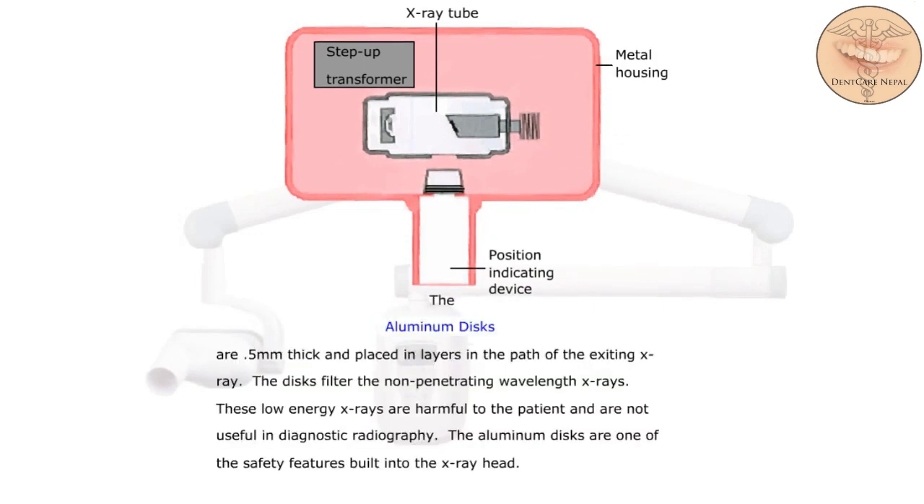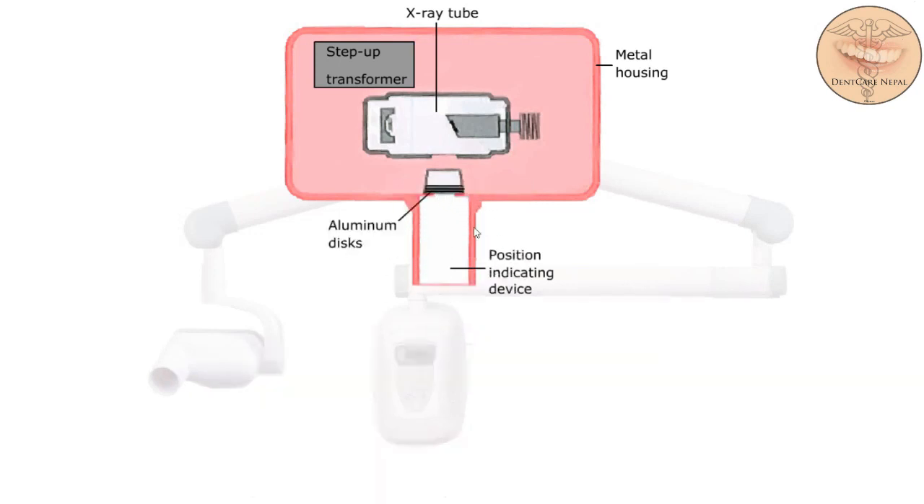The aluminum discs are 0.5 millimeters thick and placed in layers in the path of the exiting x-ray. The discs filter the non-penetrating wavelength x-rays. These low-energy x-rays are harmful to the patient and are not useful in diagnostic radiography. The aluminum discs are one of the safety features built into the x-ray head. And here are the aluminum discs.